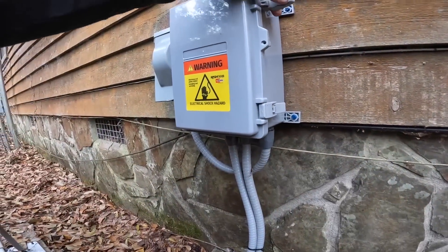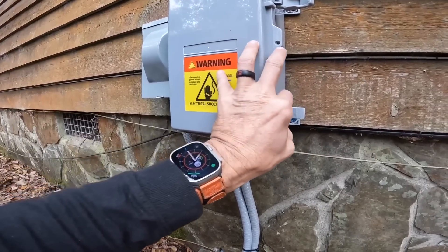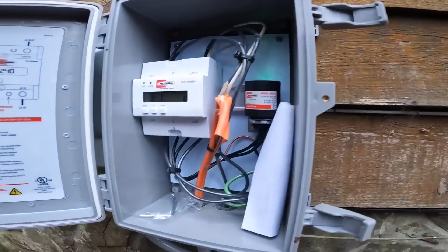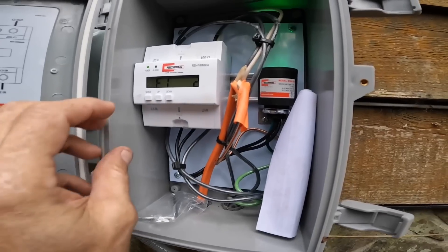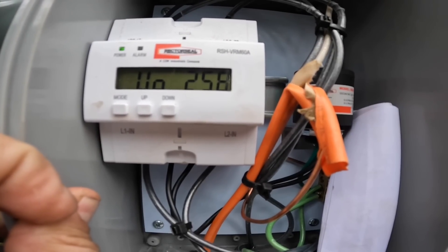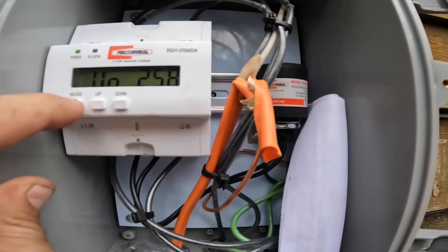First, I used this — it's a Rector Seal RSH-VRM50A kit, so it's a voltage regulator and monitor. I wanted to show you where I have it set. I have it set on 258 volts as my high and my low at 208.